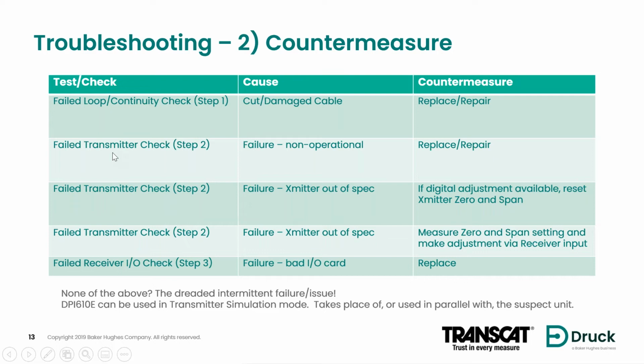If we perform step 2 in checking the transmitter and it was just dead on arrival, there was no signal, no ability to generate any signal out, it wasn't responding to pressure, obviously we would replace it or repair it. Probably the more likely scenario is having a spare and swapping it out. Or another possible failure mode in step 2 would be that the transmitter was out of specification. We found a zero or span tolerance error.